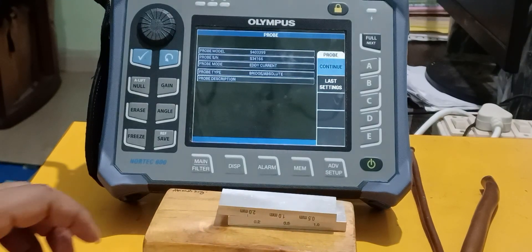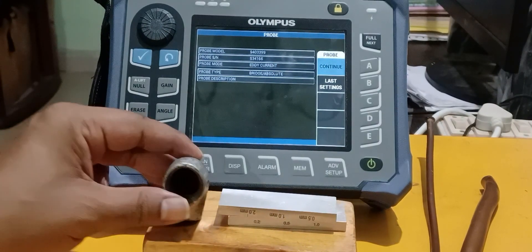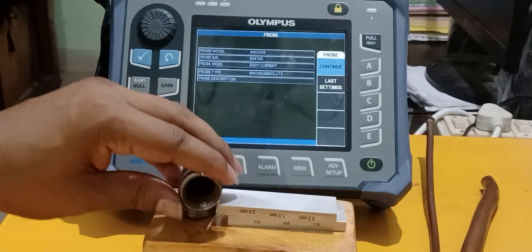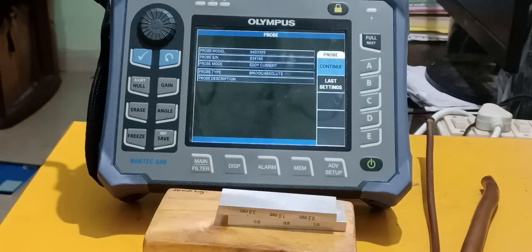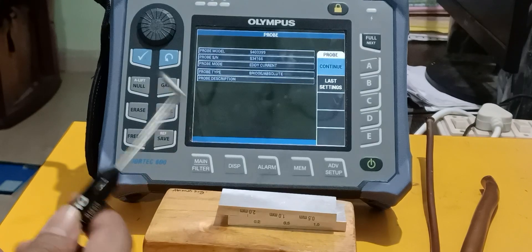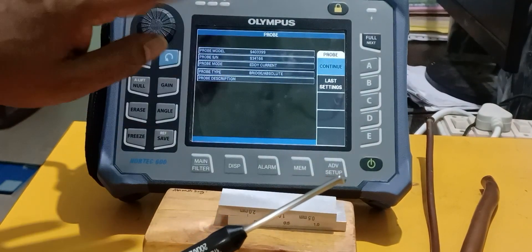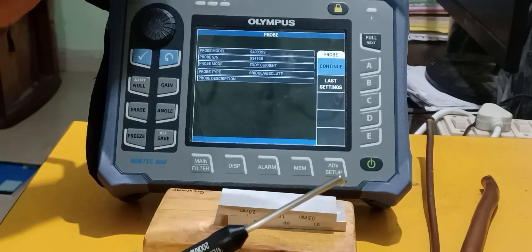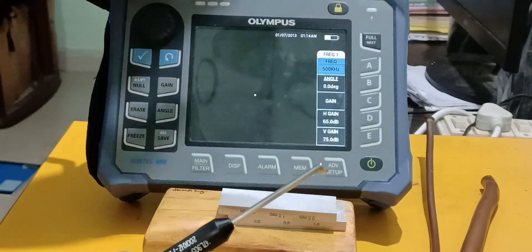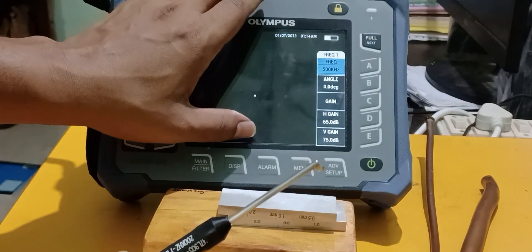Now we will work with the different materials and observe how conductivity varies across them. We will draw a conductivity locus. I have connected a probe rated from 200 kilohertz to 1 megahertz. It has an auto detection mode — it will detect the probe automatically, and we press the continue button to proceed to the impedance locus screen.